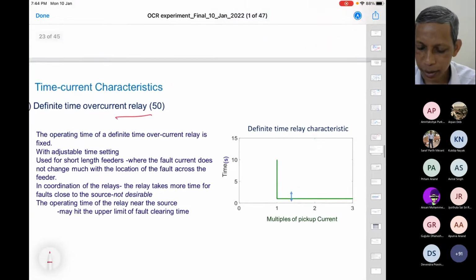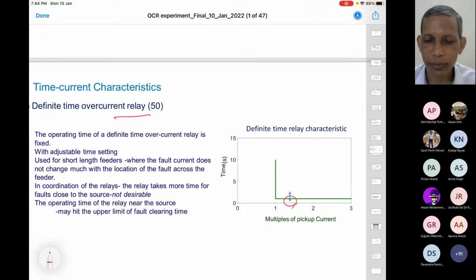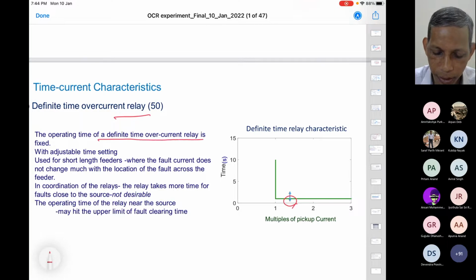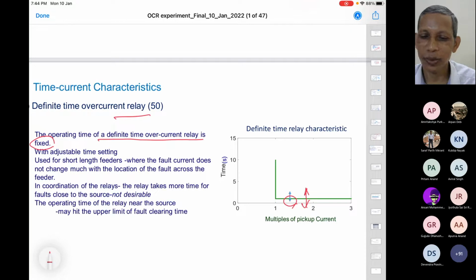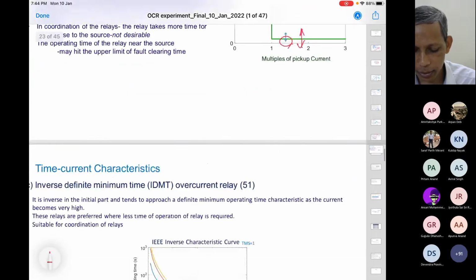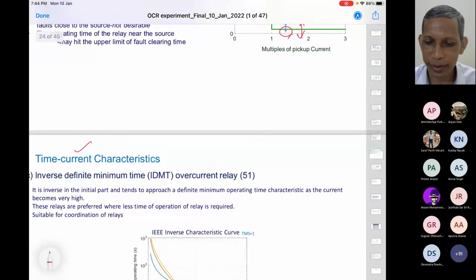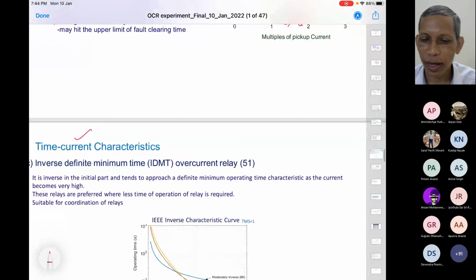Similar to that, but here it keeps some time. The operating time of the definite time over current relay is fixed. We put in a delay, which is useful in some applications. We have flexibility in changing the delay, high or low, because of different application requirements. Agree? So that is about that. Now, these time current characteristics are either no delay or with a delay.